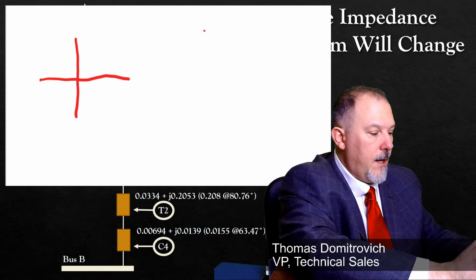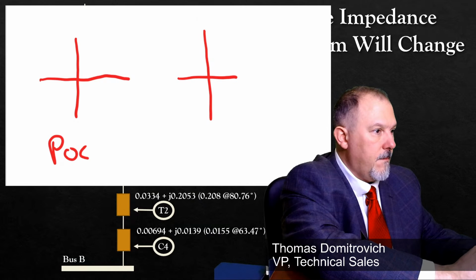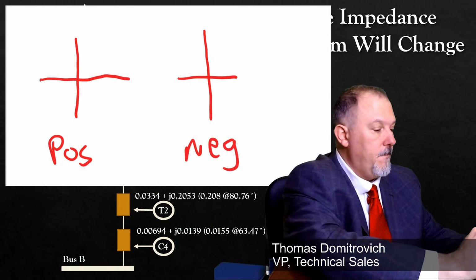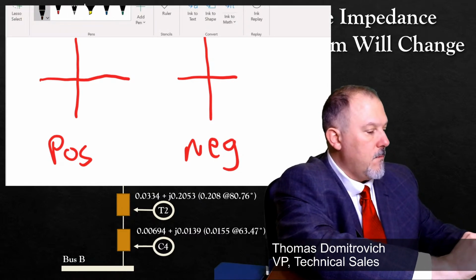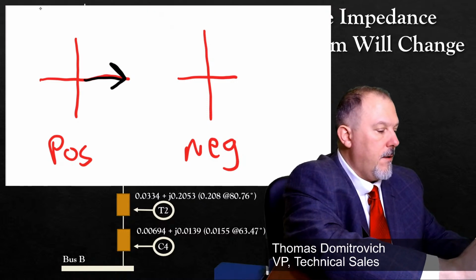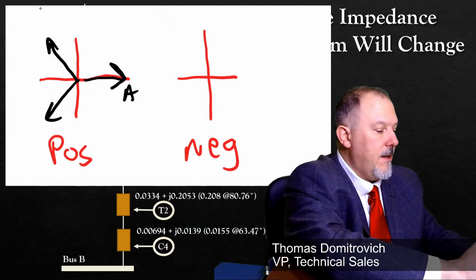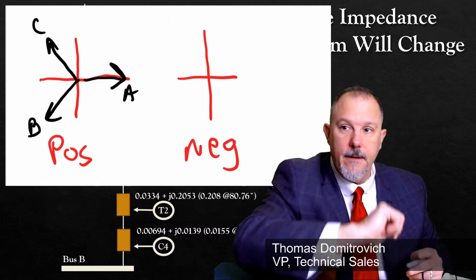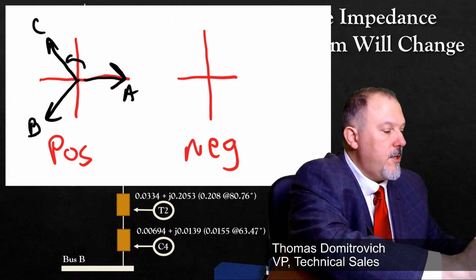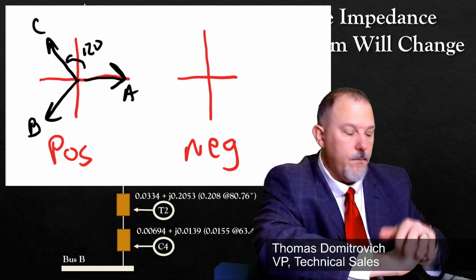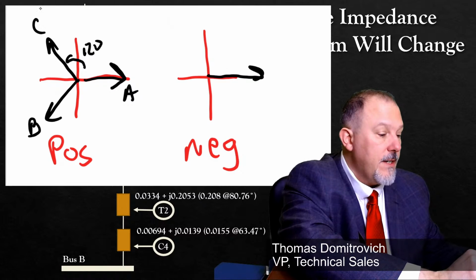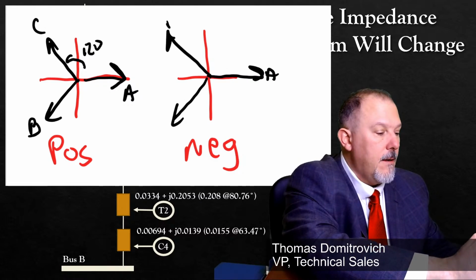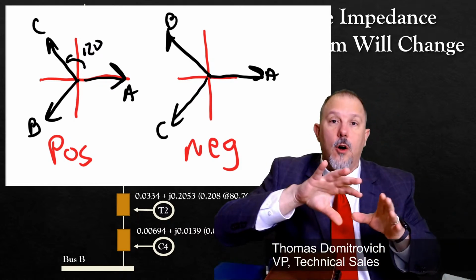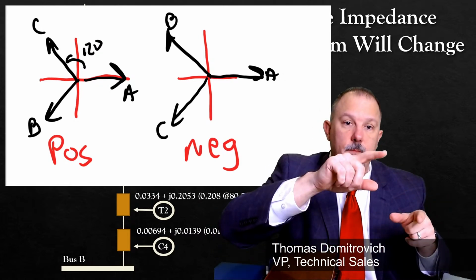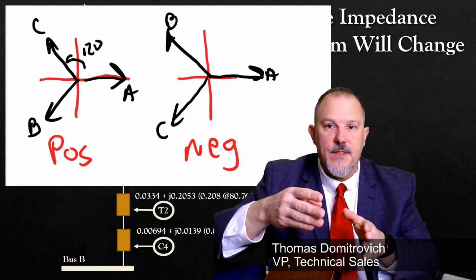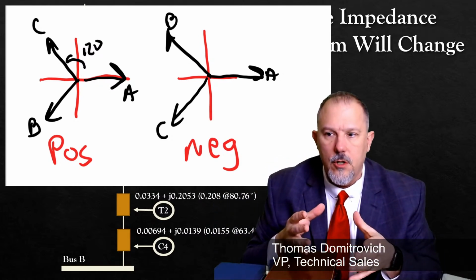If I think about the 3 sequences, so you have 1, 2. So I'm going to say this is positive, this is negative sequence impedances. I know I have phase A, phase B, phase C, counterclockwise, right? A, B, and C. And we know that the distance is 120 degrees, right? And we already talked about that. 120, 240, 0. The negative sequence is very similar, but it's A, C, B, a different phase rotation. They still are 120 degrees apart from each other. The positive sequence goes counterclockwise ABC, and the negative sequence clockwise is ACB. So you have 2 fields going in opposite directions.